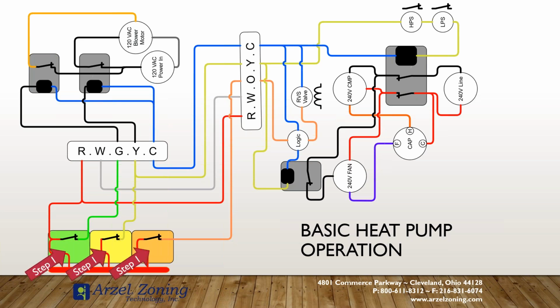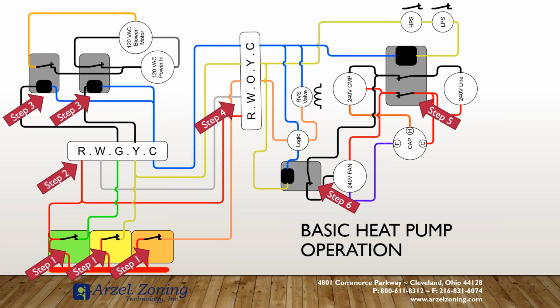start at your thermostats. From the thermostats, we move to the equipment. From the equipment, it should be pretty obvious that our blower starts. And then once we've proven that, we can now move to the outdoor unit, to the defrost board. And at the defrost board, we're going to determine, do we have our voltage out there? If we do, we need to see what's running. Did our contactor close? If it didn't, then we probably have a high pressure or a low pressure switch that's going to be open. But there's really a lot to take a look at with the defrost board, but it's still all exactly the same. It is your relays, it is contacts, it is a low voltage controlling a high voltage source.